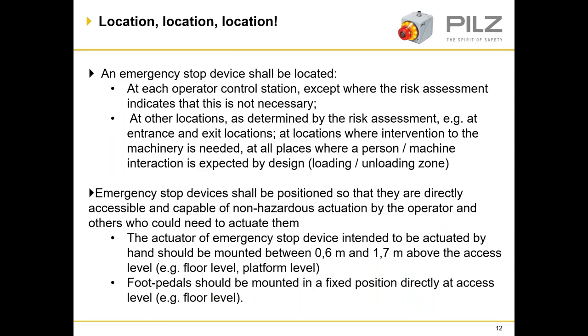Location, location, location — this really matters. An emergency stop shall be located at each operator control station, except where the risk assessment indicates that this is not necessary. Also at locations determined by the risk assessment — for example at entrance and exit locations, at locations where intervention to the machinery is needed, and at all places where a person and machine interaction is expected by design, such as loading and unloading zones. Emergency stop devices shall be positioned so that they are directly accessible and capable of non-hazardous actuation by the operator and others who need to actuate them.